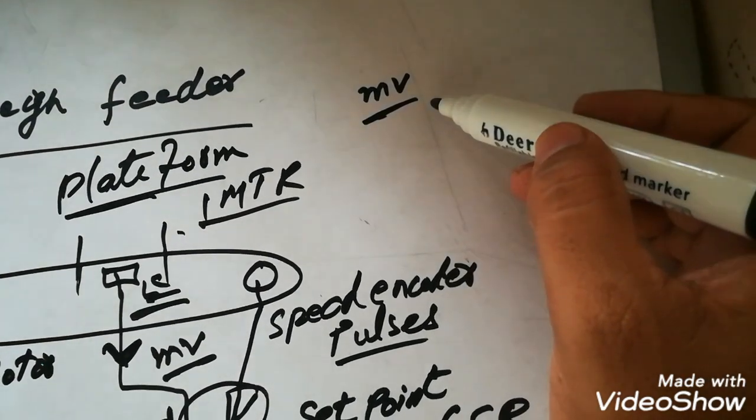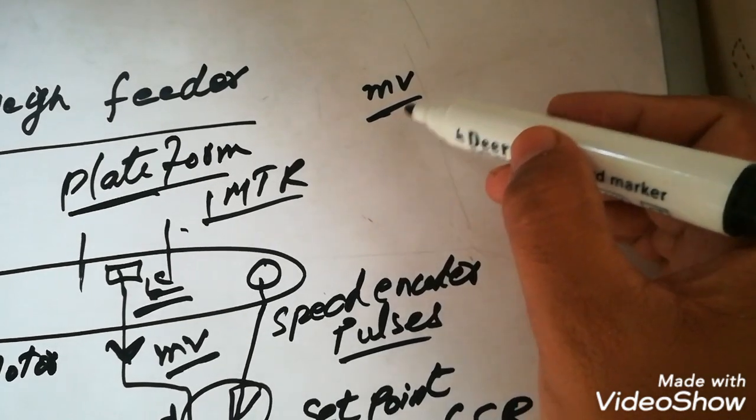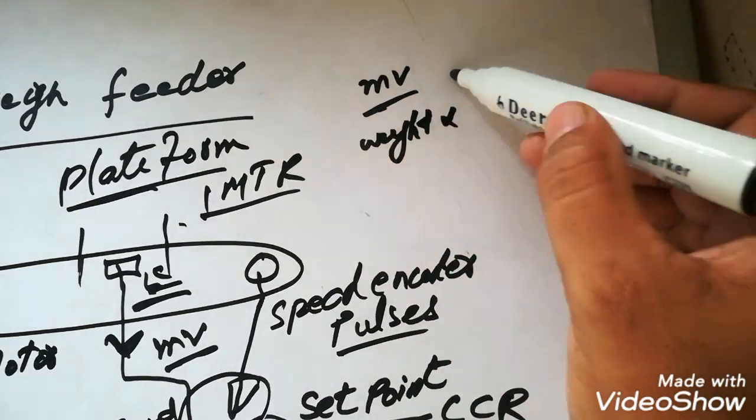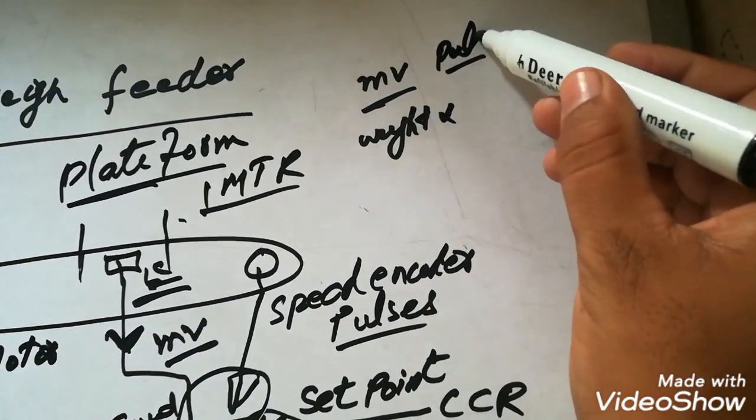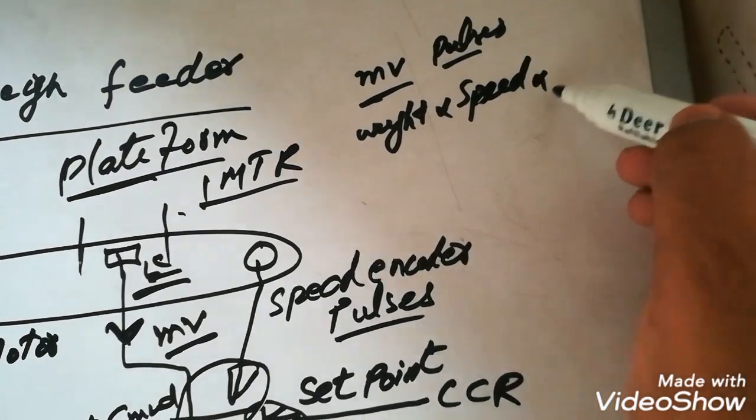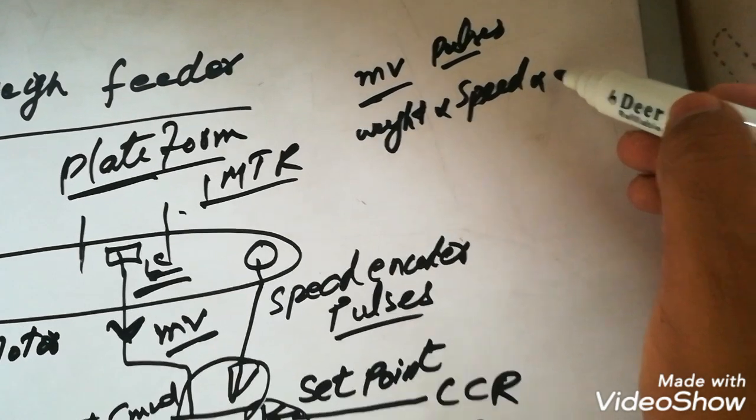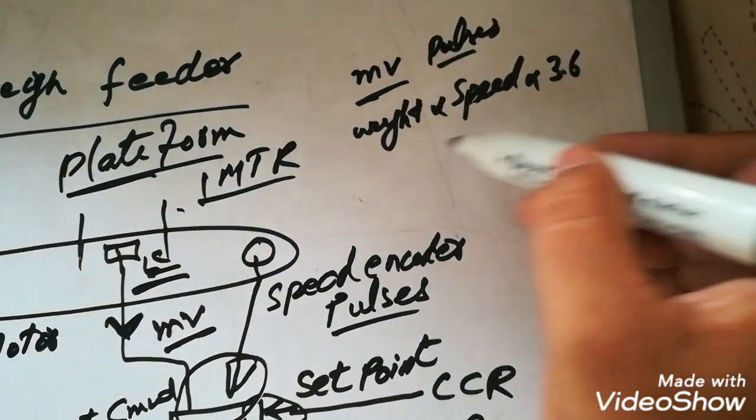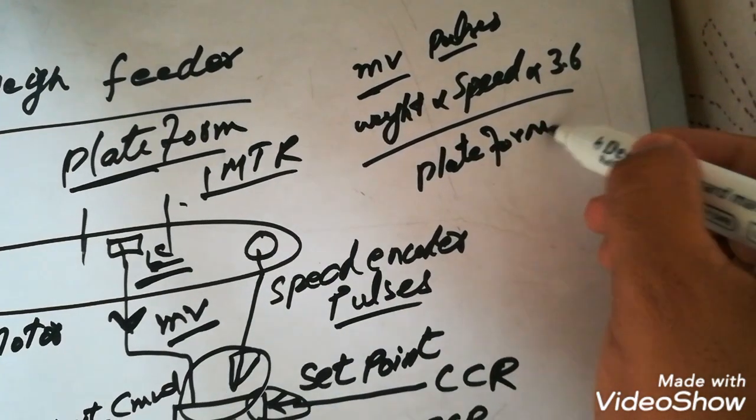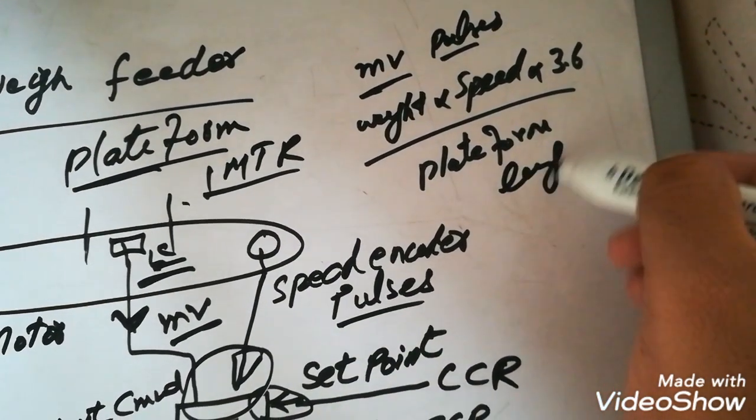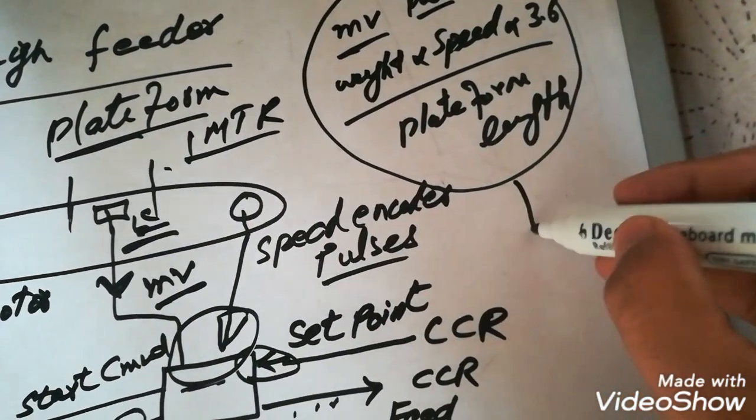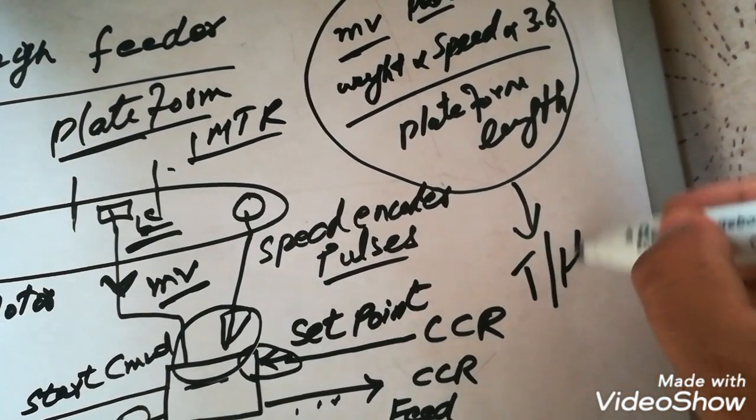How this controller calculates the load in ton per hour? It takes the millivolt, this is our weight, and the pulses from the encoder is our speed of the weigh feeder. As you know, our ton per hour is weight multiplied by speed multiplied by 3.6 divided by platform length. So this is the formula to calculate the ton per hour of the weigh feeder.